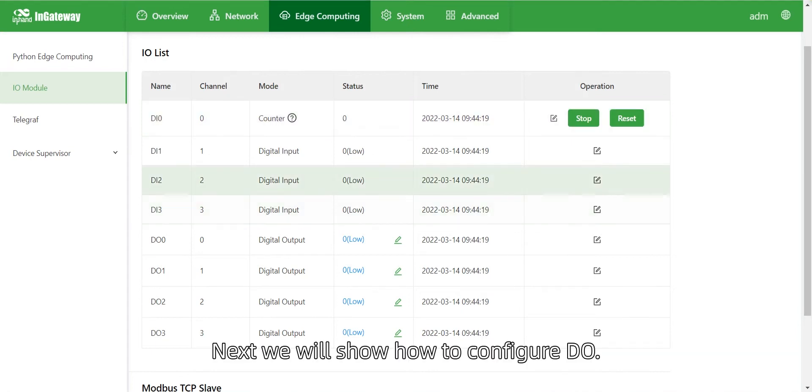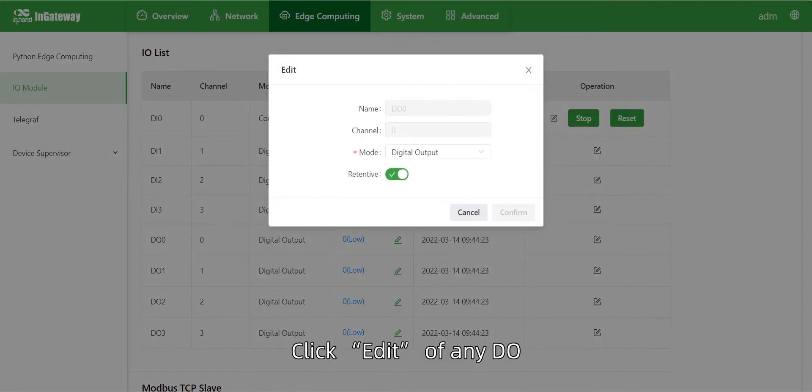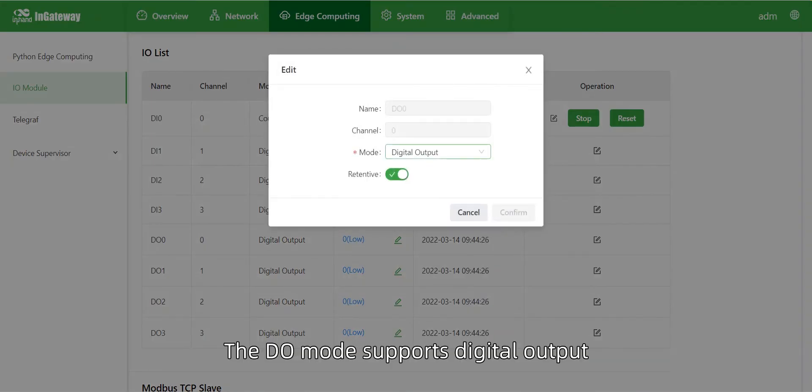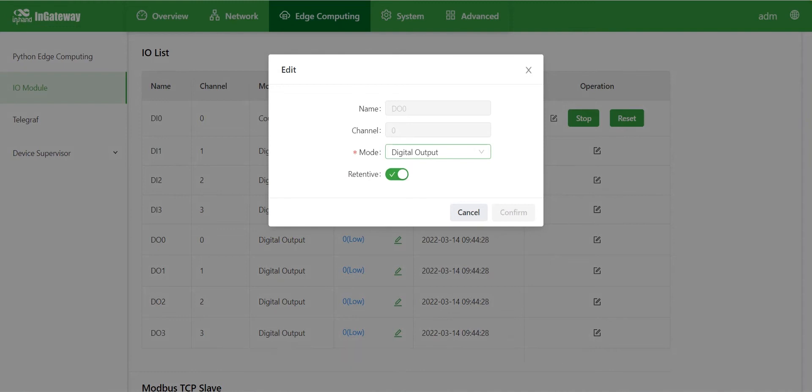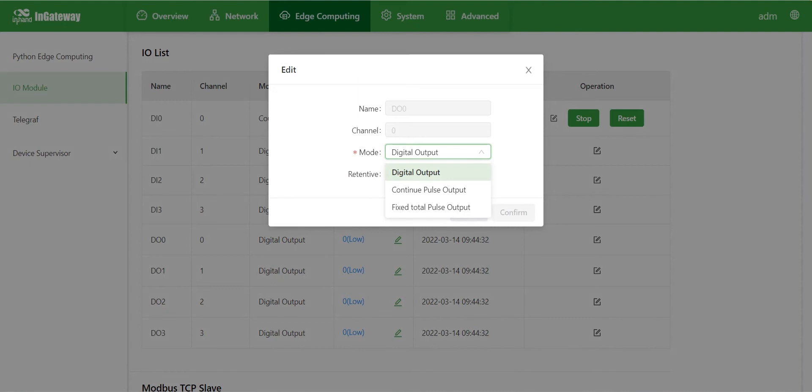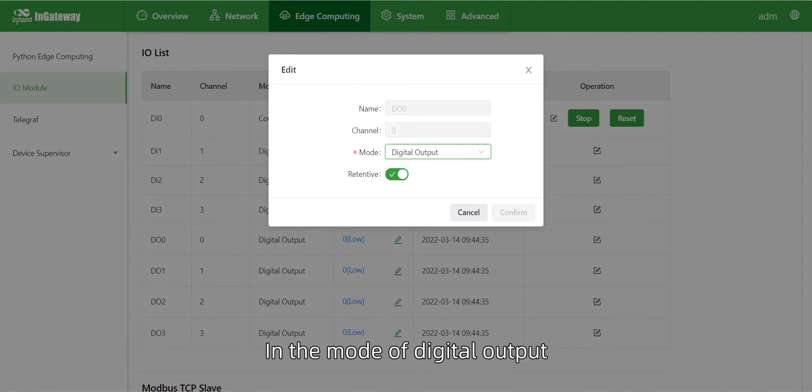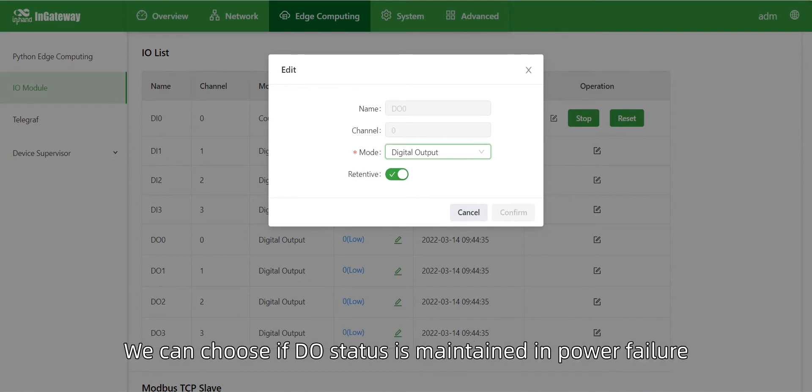Next, we will show how to configure D.O. Click Edit of any D.O. The D.O. mode supports digital output, continuous pulse output, and fixed total pulse output. Digital output refers to output of high and low electrical levels. In the mode of digital output, we can choose if D.O. status is maintained in power failure.